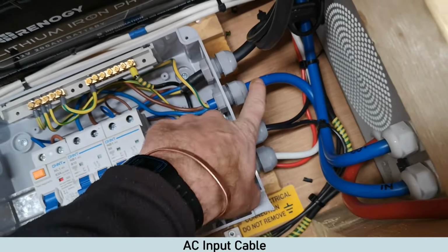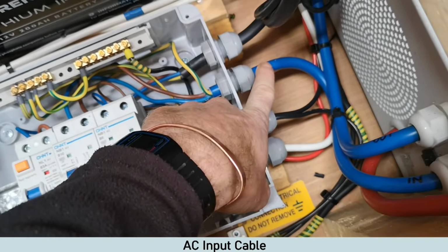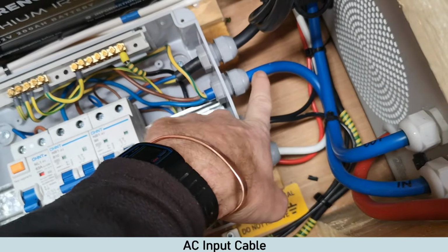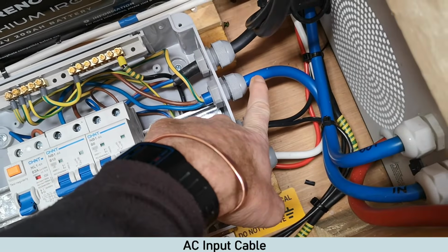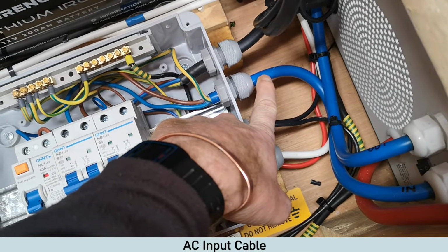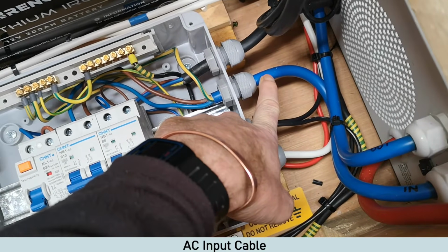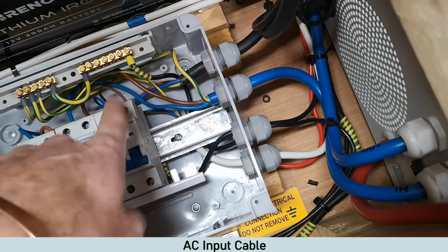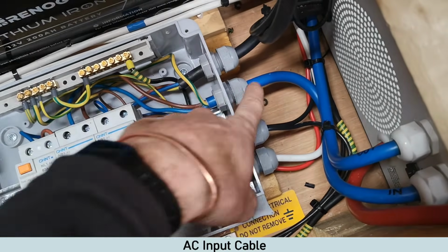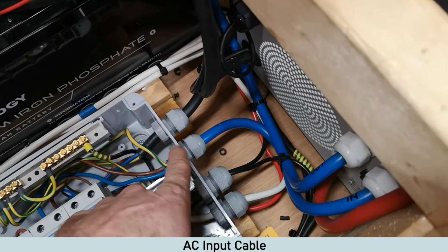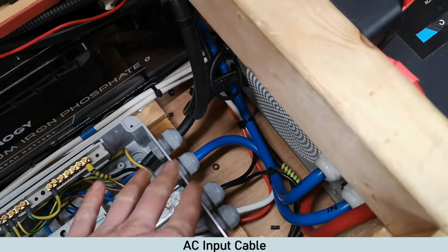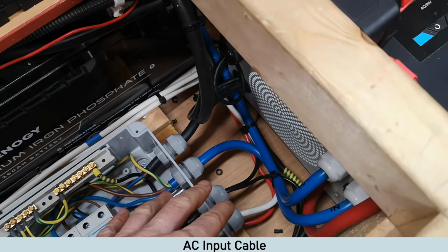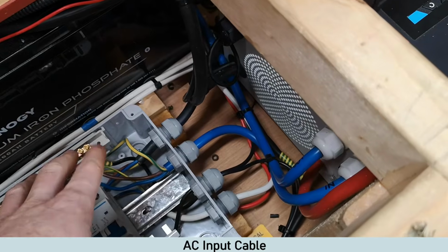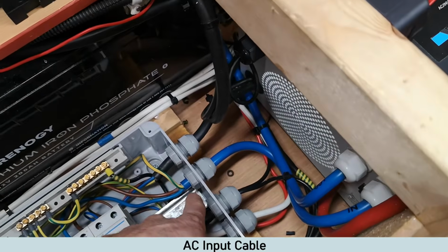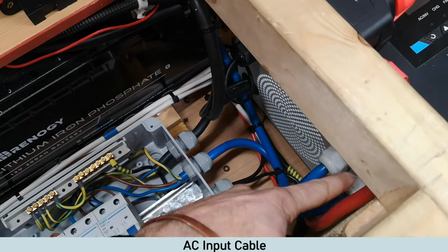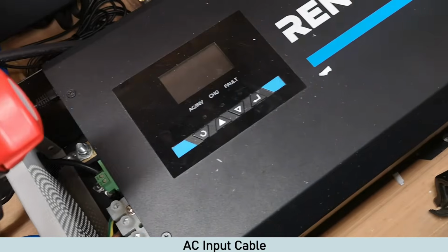Now we've used a 6mm 3-core flex for this. The reason why we've used 6mm is because we had some left over from another circuit, so we've just whacked it in. It's a big cable, we can fit it in, it fits in the breakers, so that's why we've used it. You will get away with 2.5mm cable, as long as the run of cable is not too long. So do ensure you do your cable calcs with your volt drop and everything. But 2.5 cable is generally okay to feed this unit.